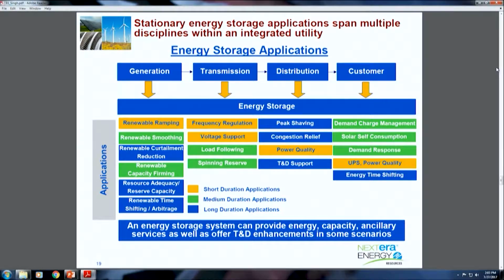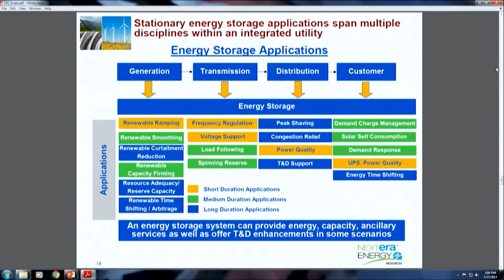For example, the first box under generation says renewable ramping. A utility on an island with a lot of solar penetration, when cloud cover comes in, sees the frequency drop. So one utility wanted to arrest the frequency drop and control it on the way down, and when the solar cloud goes away, control the ramp up too. So I don't need a 4-hour battery for that, it's what I call a short duration battery, or Reg D in PJM, which is a 15 to 30 minute battery.